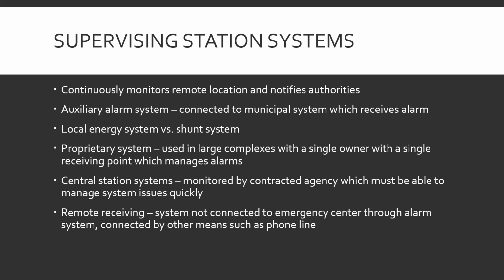That's the book definition, and kind of piecing it together, to me it sounds kind of like the auxiliary alarm from earlier above, but instead of being the alarm panel itself, it's wired into the dispatch system. It's tied in through a more simple means. So the fire alarm goes off, goes through the little phone line to the dispatch, like any other phone line, and they answer the phone, and it says something like 123 Main Street, general fire alarm, where they can't really see a whole lot of the information. It's a less high-tech way to get this alarm over to the proper people.